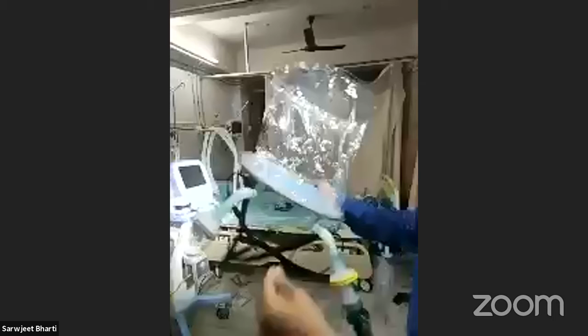If you see this helmet, this is the transparent hood part of the helmet. Ideally, this should be at least about 10 to 12 liters in capacity, a hood that is twice the total lung capacity of the patient. This will have multiple ports here. This helmet that I'm showing here has two ports. One is the inlet and one is the outlet. This is the inlet that is connected with the HME filter to maintain heat, humidification, and also reduce the noise level. Whenever you use a bubble helmet, there'll be a lot of noise. The noise level can go up to 100 dB. So to reduce that also, this is helpful. Apart from heat and moisture, it also helps reduce the noise level.